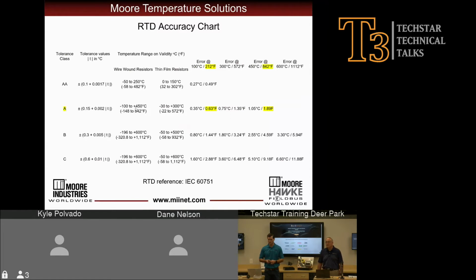So this goes back to selecting the right sensor for your application and selecting the sensor that's going to yield the best results for what you're trying to accomplish. That plus or minus 4 degrees Fahrenheit with the type J standard grade thermocouple might be perfectly acceptable for your operating conditions and application. However, if you're looking for a more precise temperature measurement and an RTD fits into the operating temperature ranges, then we highly recommend using a 4-wire RTD for that purpose.